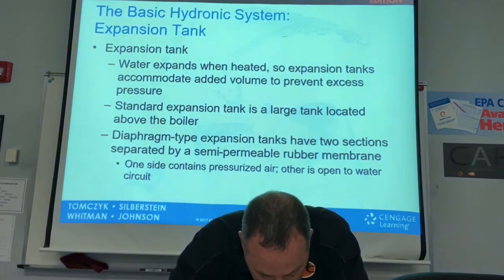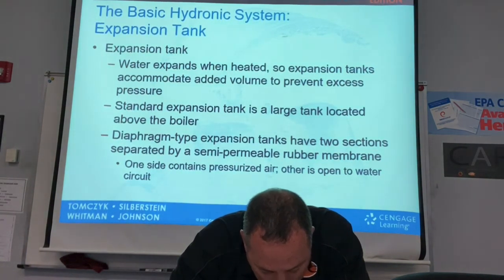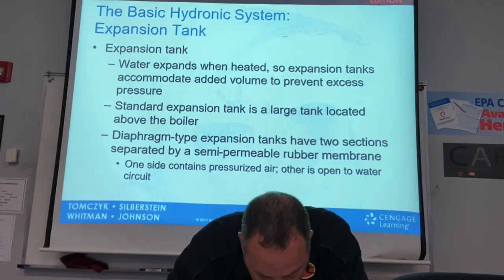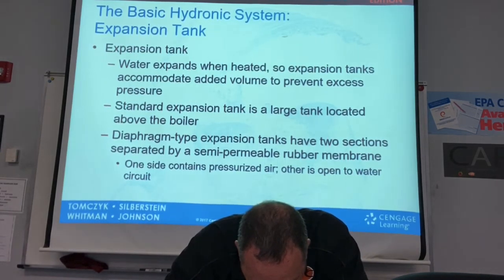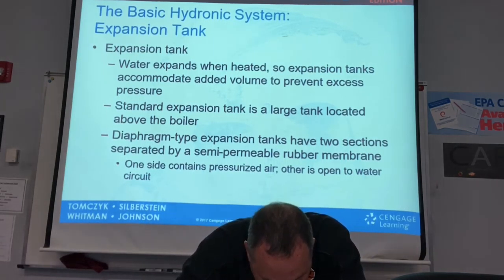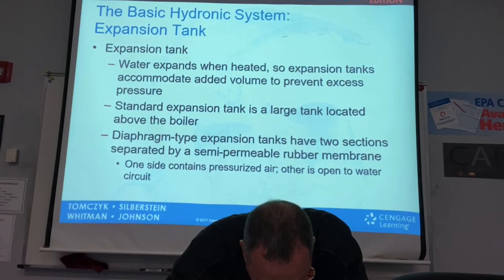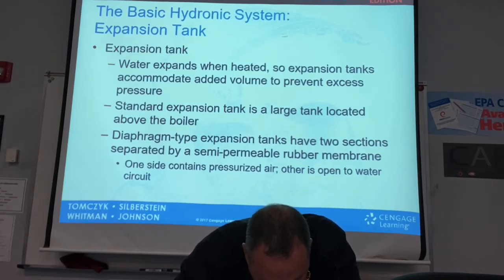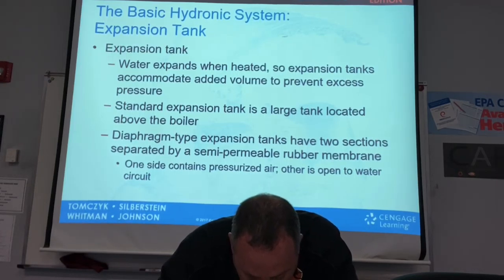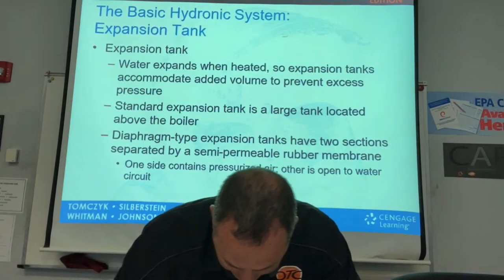The second type is the diaphragm tank, which has a rubber semi-permeable membrane inside its shell. One side contains pressurized air and the other side is open to the water. The air portion is pre-charged at the factory — normally up to 12 PSI for residential use. The tank pressure is noted on the nameplate of the tank itself, shown in figure 33.15.